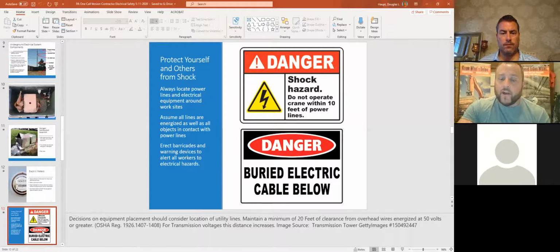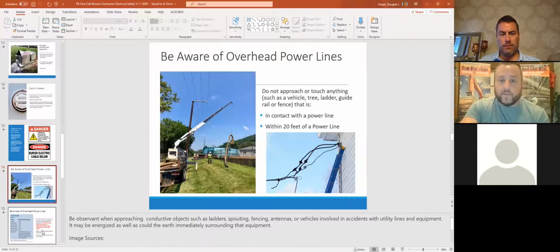In your operation with heavy equipment, cranes, and booms, remember this: if you know the operating voltage of the line you're working near, OSHA tells you to maintain 10 feet. If you don't know the voltage, you've got to maintain 20 feet from overhead facilities. I believe I have a slide coming up to show you that OSHA standard. But here's a case that didn't turn out well for these folks because they put that boom up into the outer phase of a 12,000 volt line, and injury occurred.